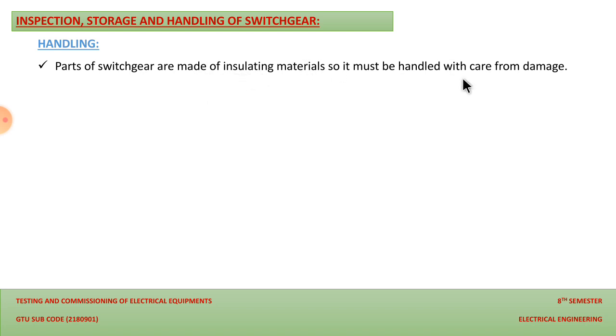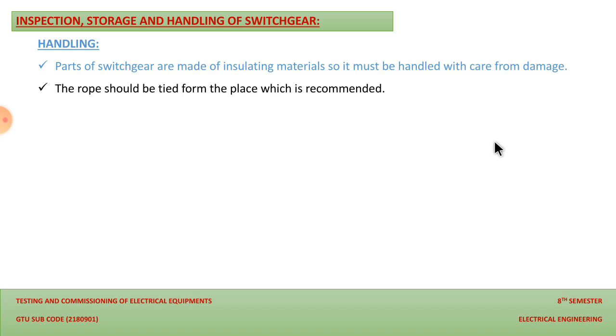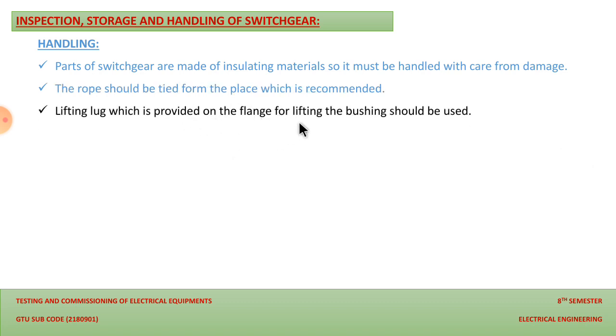And while we are keeping our instrument for future use, the next point for the handling is, the rope should be tied at the place which is recommended. On the box it is also mentioned as a caution: handle with care. According to the instructions mentioned on the box, we should use the rope and other utilities to protect our instrument from further damage. And the lifting lugs, which are provided on the flange for lifting the bushing, should be used. According to the manufacturer's instructions for the loading and unloading of the machine, we should obey all the rules and regulations for the lifting and transit of the instrument, to give proper protection to our device.